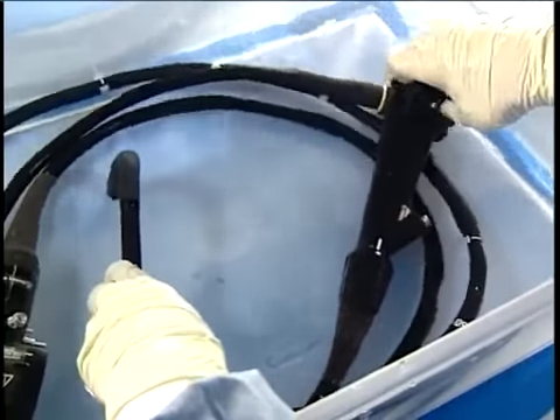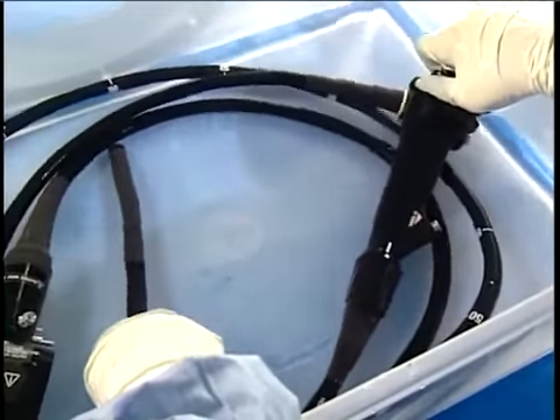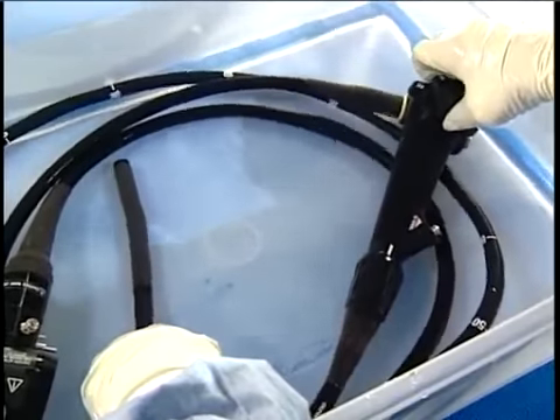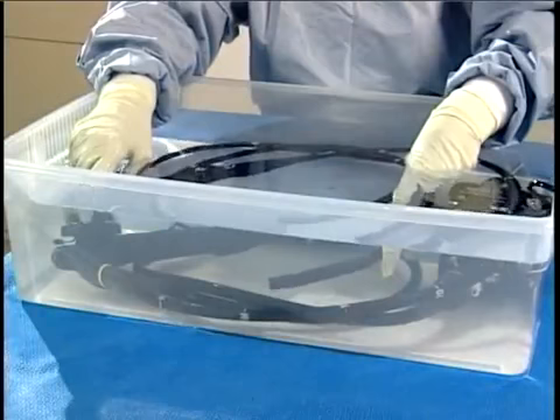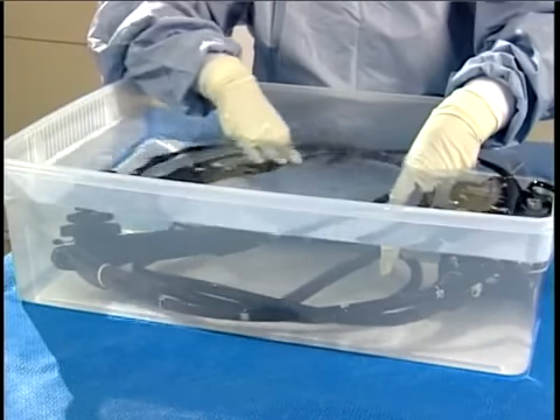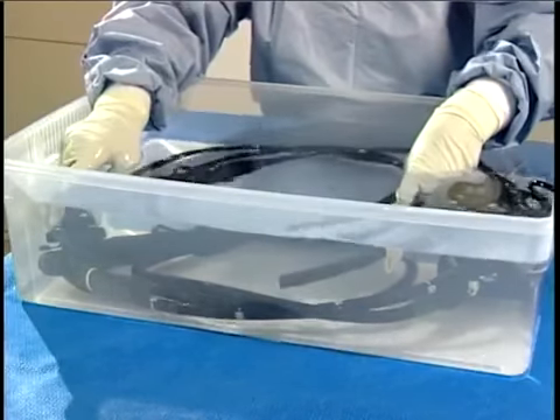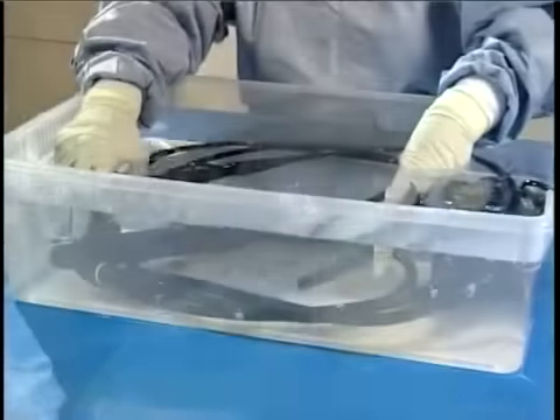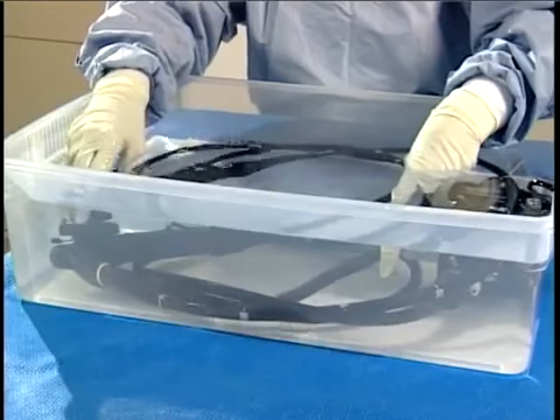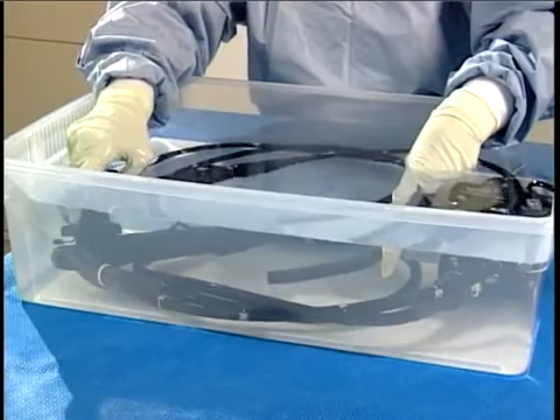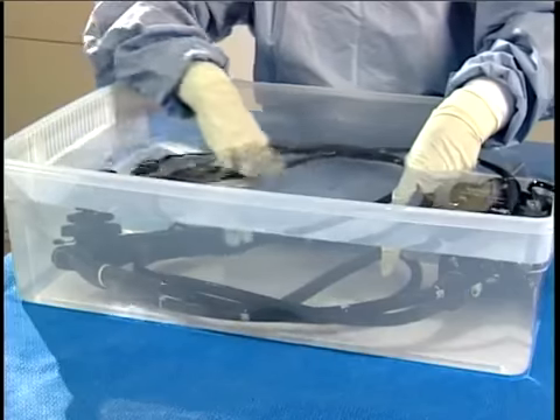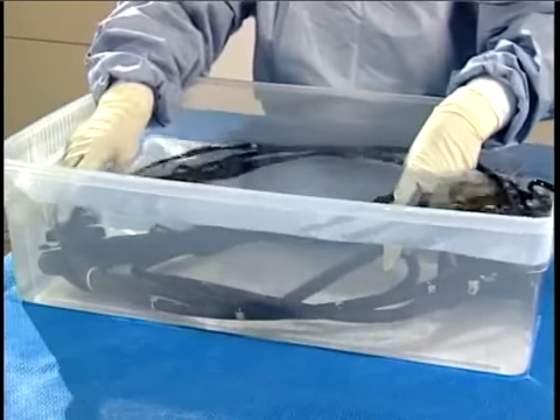Initially, you may see a few bubbles clinging to the insertion tube or coming out of a channel opening. These do not indicate a leak. Wipe away any bubbles clinging to the instrument. Also, manipulate the scope buttons to check for leaks. If you see no source of continuous bubbles, the endoscope is air and fluid tight.